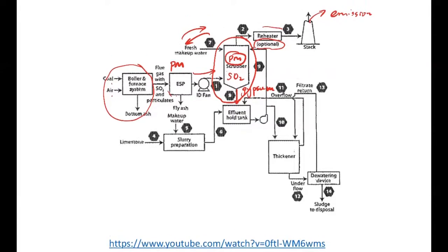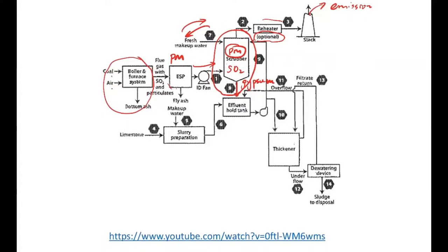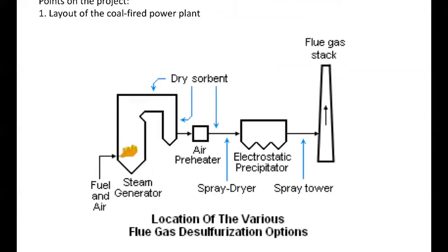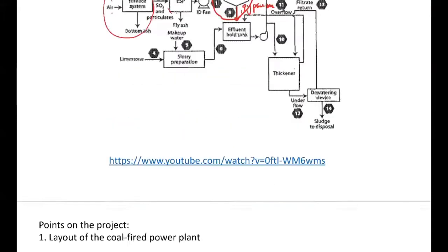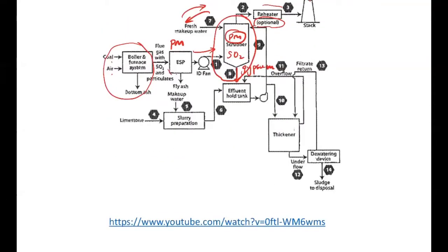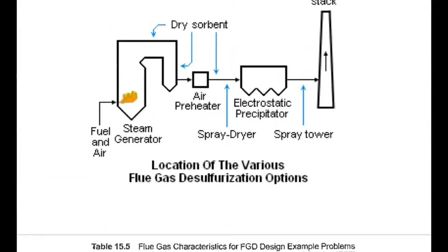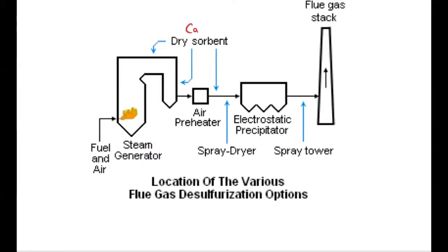And this is what happens in a limestone scrubber, but for our project, we're going to use dry sorbent injection, right? What dry sorbent injection means is, instead of using this wet scrubber or the limestone scrubber, let's just deal with all of the reaction in the gas phase. So let's just introduce lime or trona as particles. We can introduce them as solids or PM into the duct, right? Just let the particles react with the sulfur dioxide while it's flowing through the duct, okay?